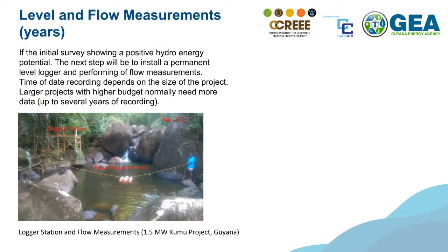Once you've found the station and the location looks good from the first survey, you start leveling and flow measurement. You need to know how much flow is going through, since you already have the head - with the head and the flow together, you have enough information to design the project. The flow measurement is done repeatedly, giving you liters or cubic meters per second, and at the same time you level the water. So if the water level is at 1 meter now, you record the flow at that level, and you repeat this the next day, the next month, and so on.